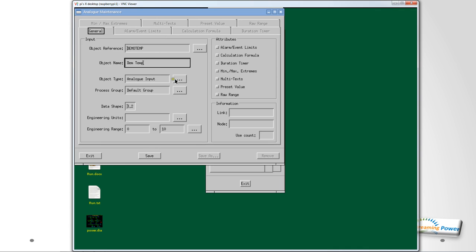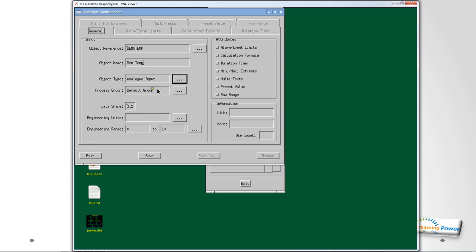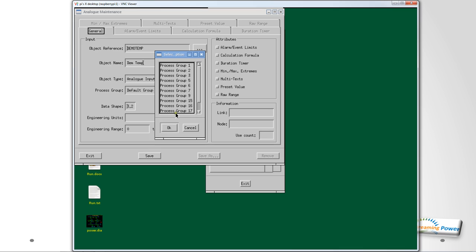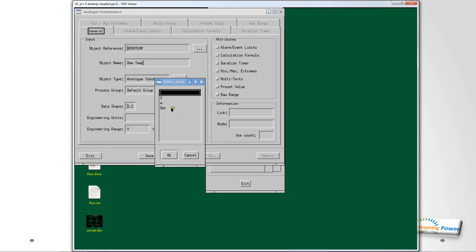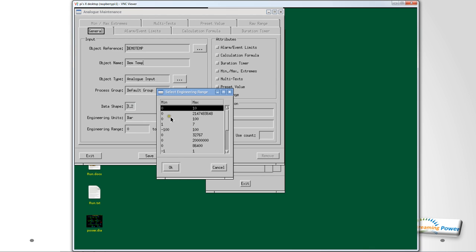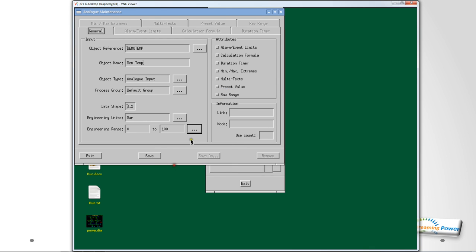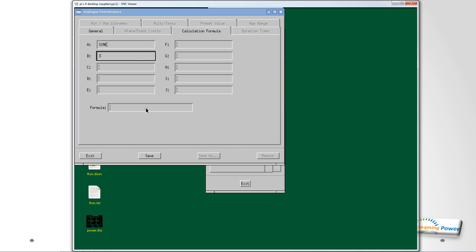So let's create one. Let's go to Analog Objects and create a new one and we're going to call it demo_temp. We give it a name. We tell it what kind it is, analog input or output, we'll leave it as an input. We can put it into different process groups if we want. We define its data shape, how it's going to be stored in the database. We can give it engineering units, for example we'll call it bar but I could put degrees C if I wanted to. We could put a range, let's say 0 to 100. So that defines the basic element.